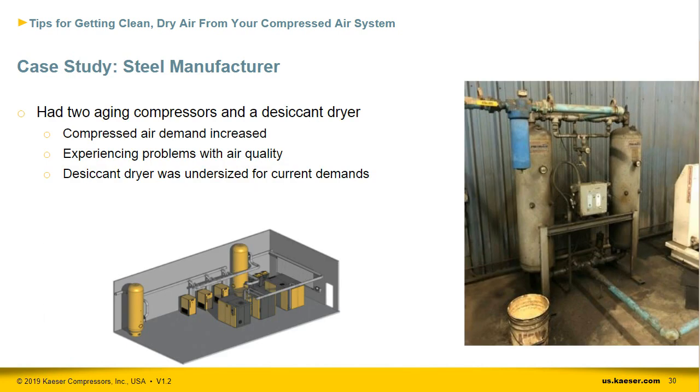Now let's look at a case study where a customer had to make a decision regarding air quality. This particular customer was a steel manufacturer specializing in structural beams and supports. He had two existing aging compressors and a heatless desiccant dryer in his compressed air system. His compressed air demand had increased over the past years, and he began experiencing problems with air quality to the point that there was liquid water in his compressed air pipe.